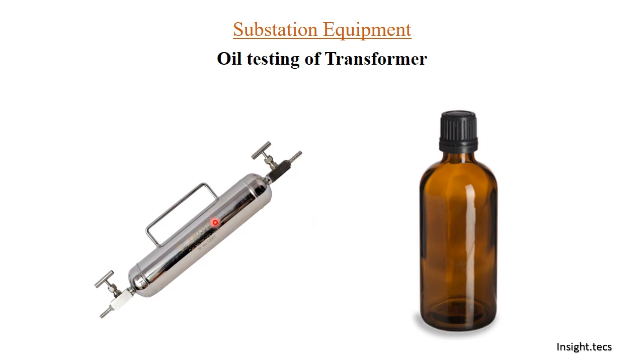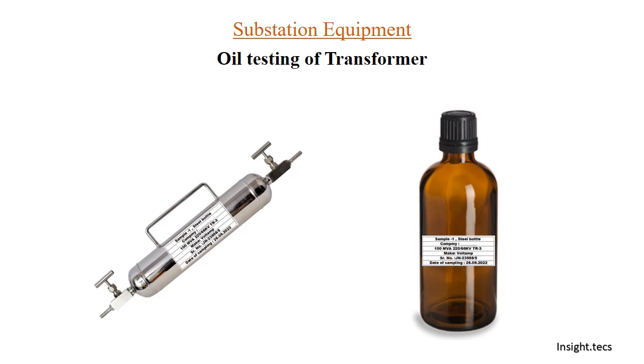Both samples are now taken: the steel bottle is used for DGA and the glass bottle is used for routine testing. The very important things to take care of are that both bottles should be cleaned very thoroughly with oil before taking the sample, and there should be no gas bubbles or gases present inside the sample while taking it from the transformer. After taking the sample, we do labeling on the bottles — indicating which transformer the samples are taken from, its make, and every other detail including the sampling date. Once labeling is done, you can send the samples to any oil testing laboratory and they will perform the different kinds of oil testing according to the standards mentioned.